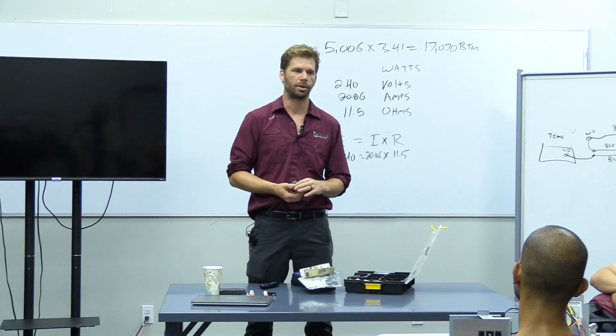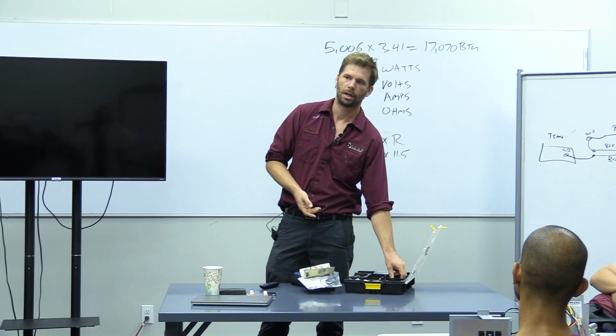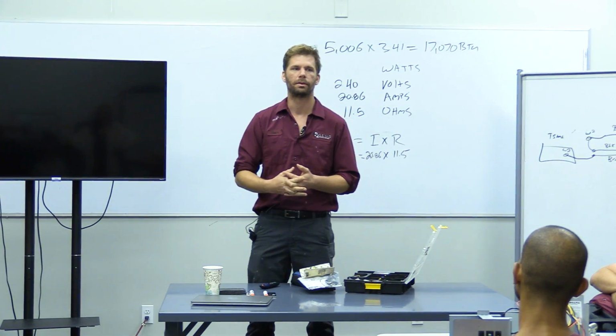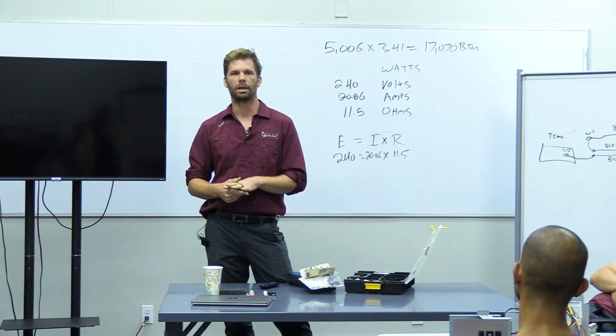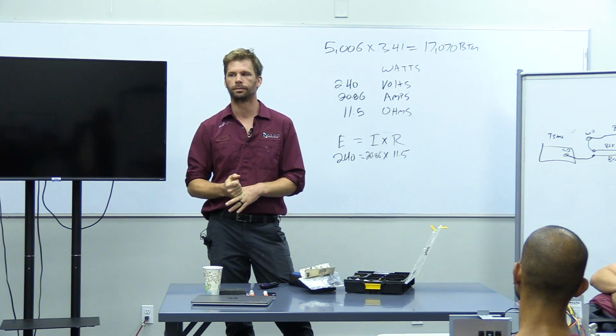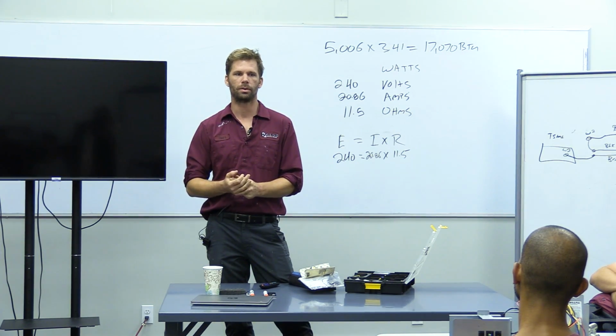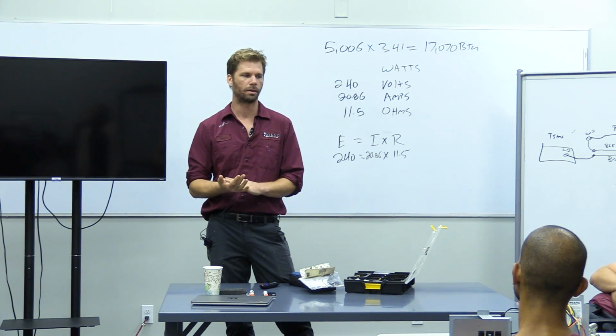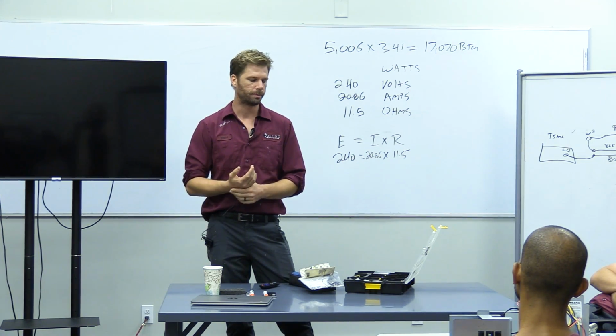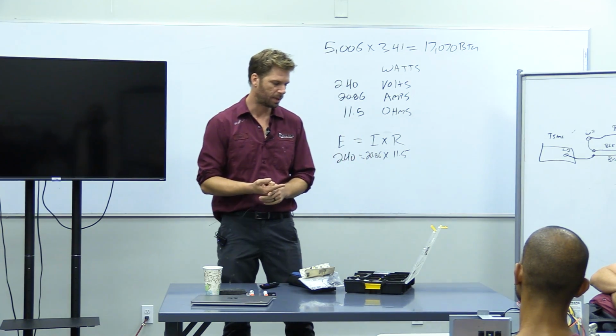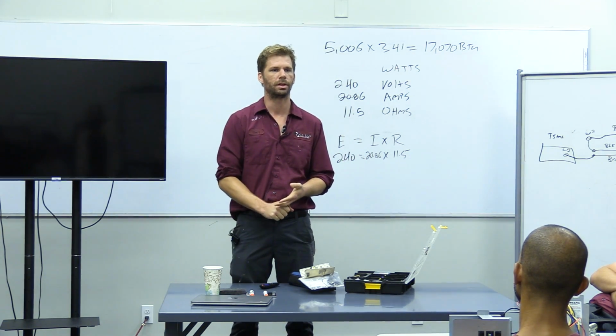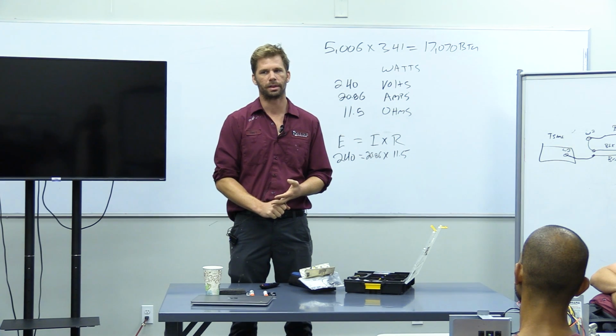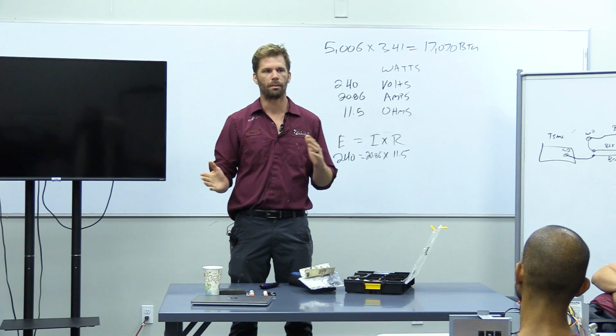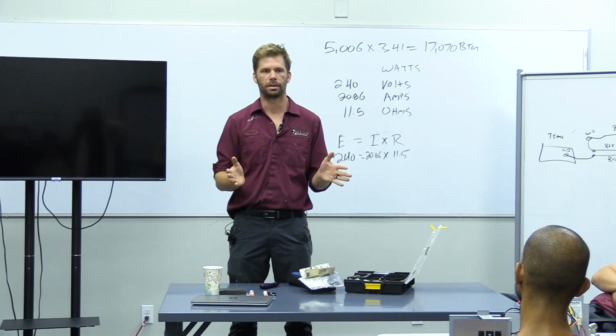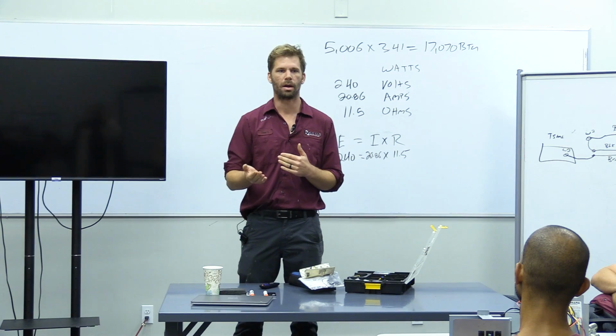And why would you have high pressure, like a high pressure error code, refrigerant error code, if you have a clogged filter? Not enough water. Yep, and what's the connection there? Water cools the refrigerant. Yeah, water cools the refrigerant. So you don't have that good water flow, you're gonna go up on high pressure. You do find that you're gonna be replacing low pressure, high pressure switches more commonly on pool heaters than I would say on ACs, because there are just a lot more situations where they're going out on their pressure switches. So those pressure switches are being used a lot more often.